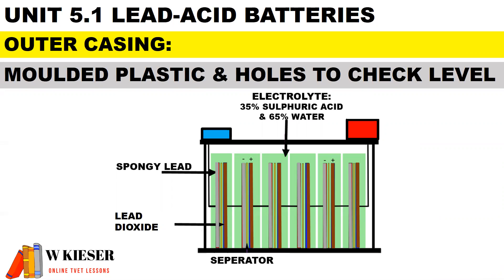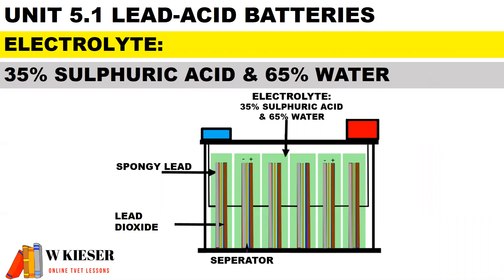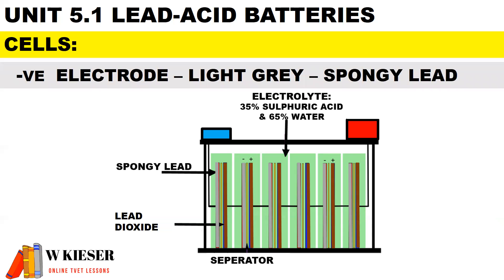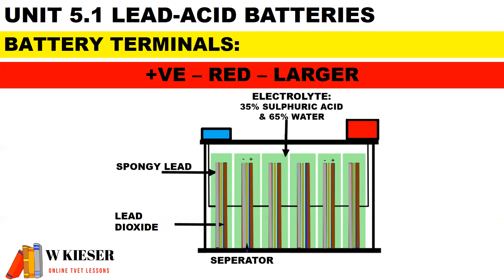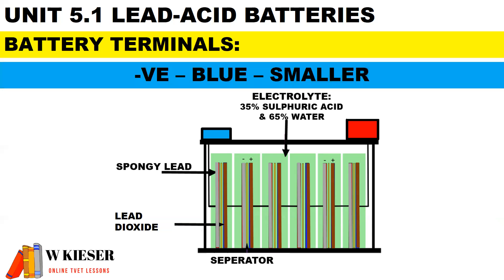The outer casing is molded plastic and there are holes to check the electrolyte level. The electrolyte, when fully charged, consists of 35 percent sulfuric acid and 65 percent water. The negative electrode is light gray in color and is made of spongy lead. The positive electrode is dark brown in color and is made of lead dioxide. The positive terminal is red and larger, and the negative terminal is blue and smaller.